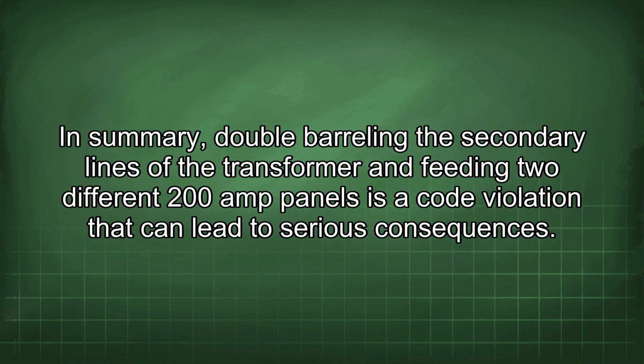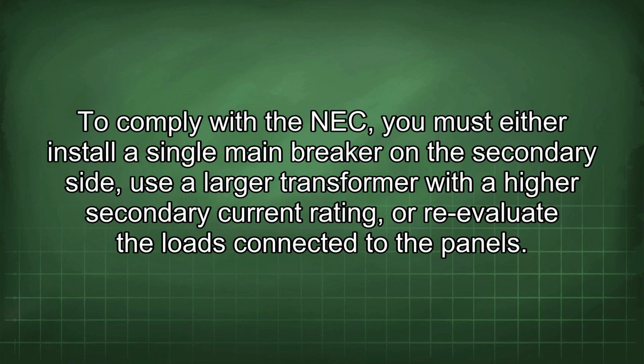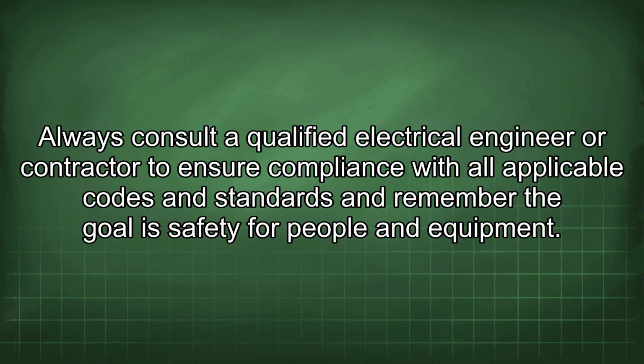In summary, double barreling the secondary lines of the transformer and feeding two different 200 amp panels is a code violation that can lead to serious consequences. To comply with the NEC, you must either install a single main breaker on the secondary side, use a larger transformer with a higher secondary current rating, or re-evaluate the loads connected to the panels. Always consult a qualified electrical engineer or contractor to ensure compliance with all applicable codes and standards, and remember the goal is safety for people and equipment.